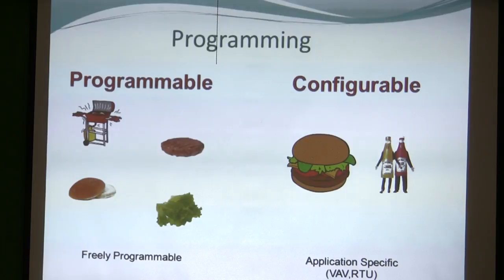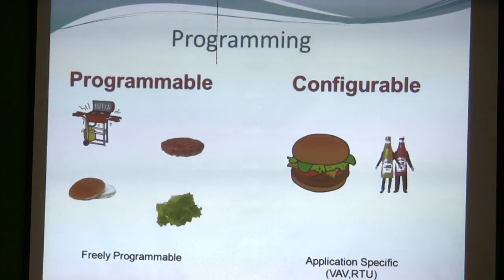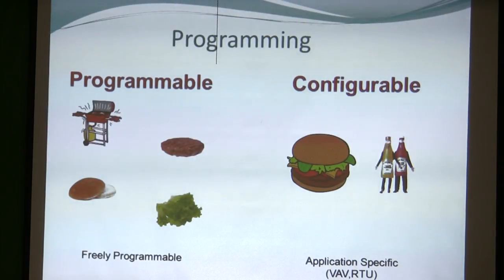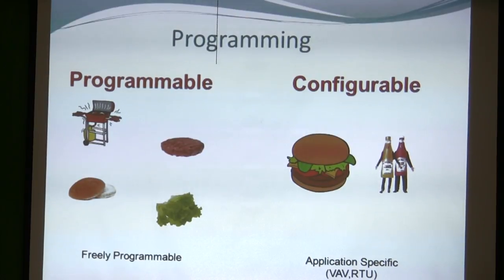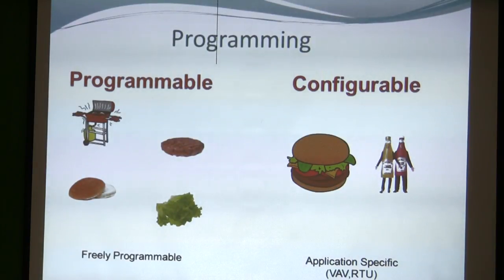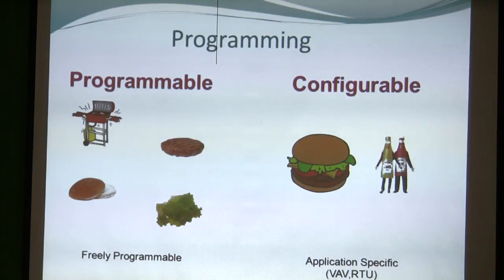A lot of times a configurable controller is going to be application-specific — for a VAV, for example. Because you're doing hundreds of boxes that are all going to be pretty much the same program, the last thing you want to do is start from scratch every time. If you can just take what you've already done and pop it into something else, you cut your time by 90%.